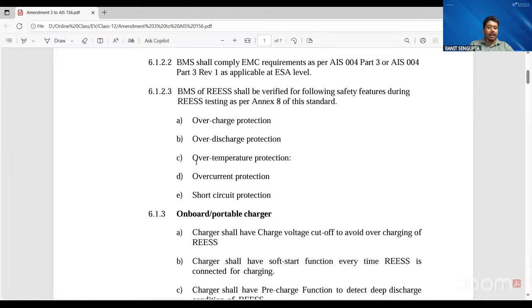Now there is onboard charger or offboard charger certification. Suppose we are using an onboard charger, or there's a portable charger - the charger shall have voltage cutoff for overcharging, that is the last charging algorithm, or the charge termination point. In the algorithm we have trickle, then pre-charge, then CC, then CV, then charging termination. After getting the communication, after getting the BMS data, the charger should stop charging.